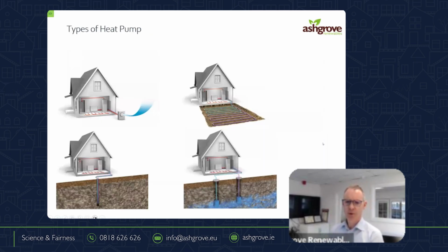So the various types of heat pump, we won't be spending time. We're all familiar today with the air source heat pump. We'll talk about ground source. We'll talk about vertical closed loop, which we would have seen a lot of 10 years ago or 20 years ago in Ireland. And then the last one, which we typically don't suggest in housing, despite the fact it's shown here in a lovely image, we don't typically like to see open loop boreholes or collectors in domestic housing. The reason is inevitably there's going to be silt and so on. We won't, as we know in Ireland, maintain it. The filters will get blocked and your COP, or your efficiency, will drop. So typically there's more maintenance here.